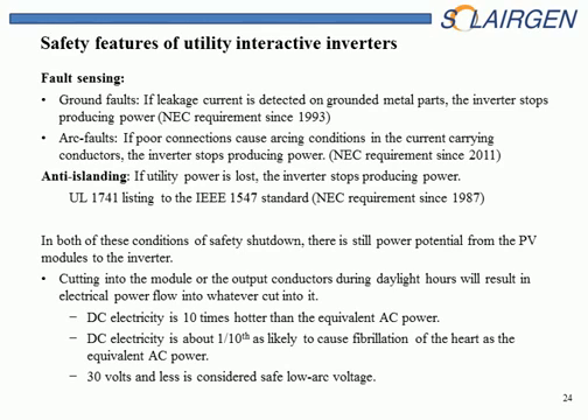So this makes it safe on the AC side, and all interactive inverters are pretty safe on the AC side. The DC side is a different matter. We still have potential on the DC side, on all PV modules and all PV systems. With the older types of systems for residential, we had higher voltage conversions. We had string inverters, and this high voltage is very hot. It's 10 times hotter than AC. It's only about 1/10 as likely to cause fibrillation in the heart, but it's still dangerous as a shock hazard.